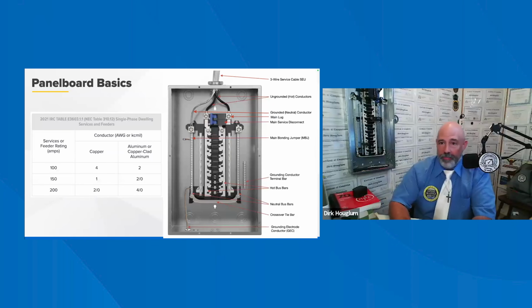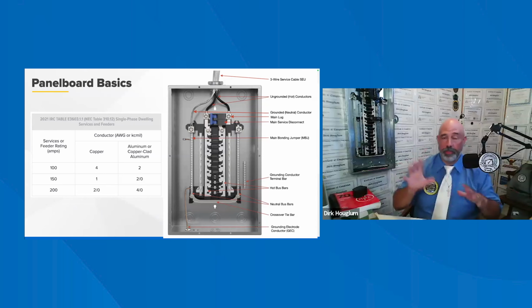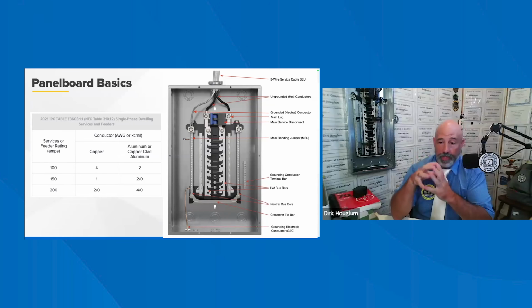Now, most inspectors, including myself, have a mental checklist when it comes to inspecting panel boards. I won't be going into that depth because of time restraints, but go back to the Electricity 101 webinar if you want to know more. Common types of panel board have an integrated main service disconnect. For these installations, there are 3-wire service entrance conductor cables from the meter to the main panel board. The cable has 2 ungrounded or hot conductors and 1 bare stranded neutral conductor. If the main service disconnect were installed at the meter outside, there would be a 4-wire SER cable from the meter to the panel board.